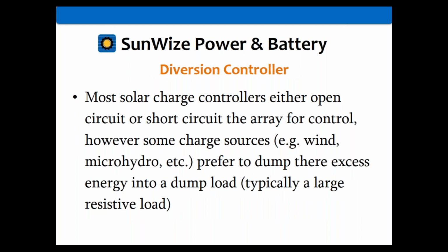Diversion controller is another feature you can do with these things. Most charge controllers either open circuit or short circuit the solar array for control. Short circuit would be the shunt regulator, and everything else just opens it, basically disconnecting the array when the batteries reach full state of charge. Some devices, though, do not like to be open circuited or short circuited.